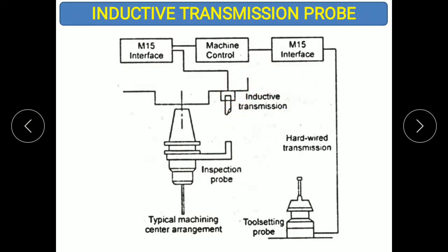In the inductive transmission probe, the probe comes in contact with the workpiece. The machine control system is the electronic part which plays an important role in transmitting the displacement signals into electronic signals. This is the inspection probe — the inductive transmission system used to sense and relay measurement data.